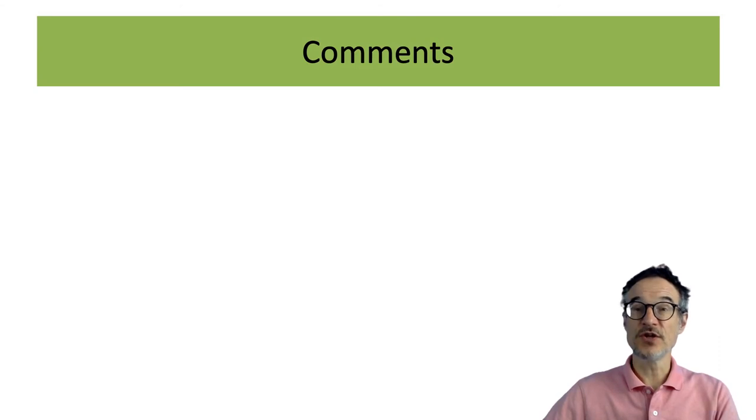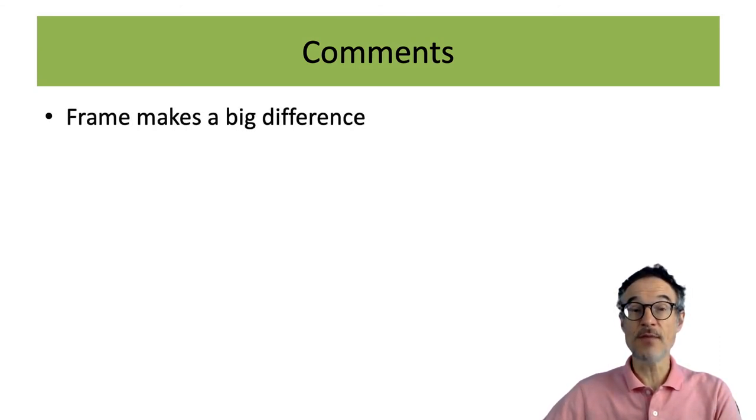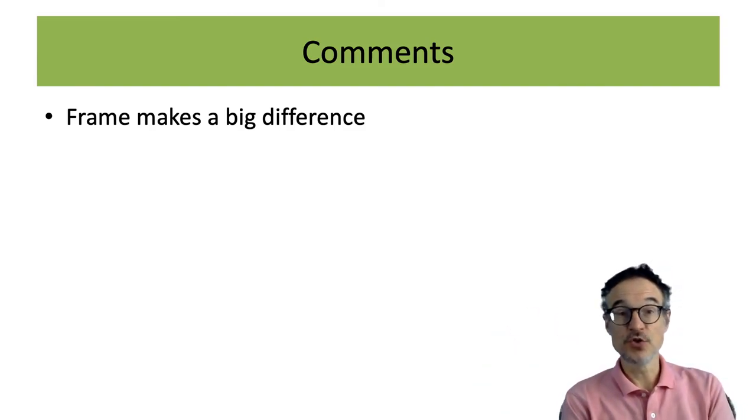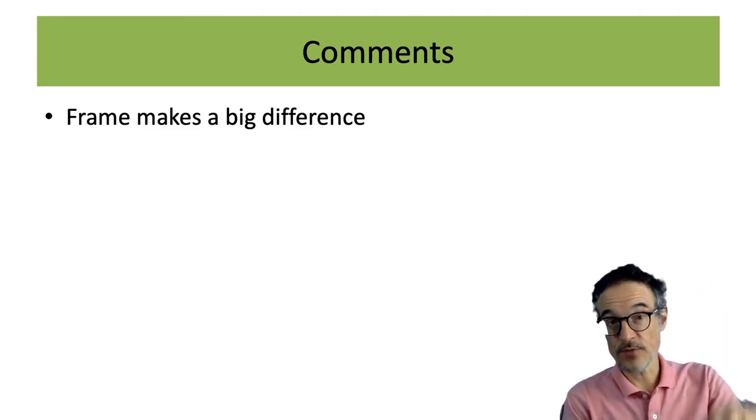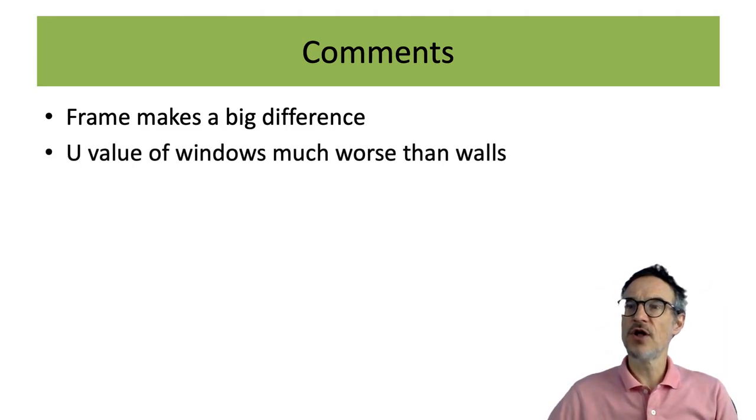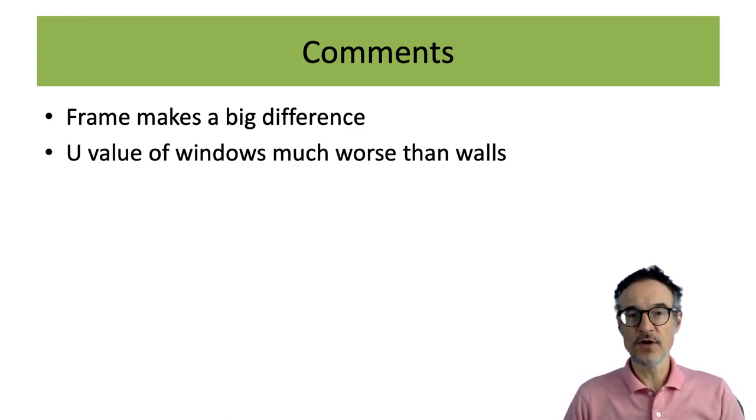A few things to notice on this: one of them is that the frame makes a big difference. So if you have a bad frame, it's going to lose a lot of heat and the performance of the windows is going to go down. And pretty much any wall that you can think of is going to have more insulation than your windows, if you put in a little bit of effort. So the U value of the windows is usually much worse than the walls, if you put serious amounts of insulation.